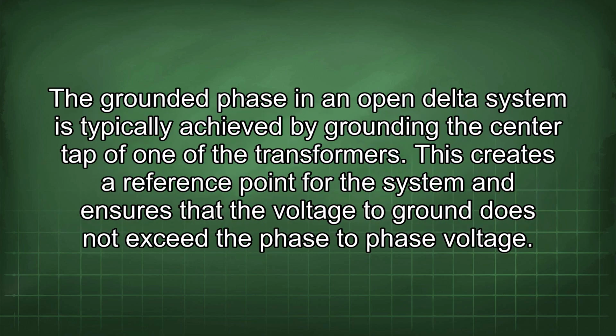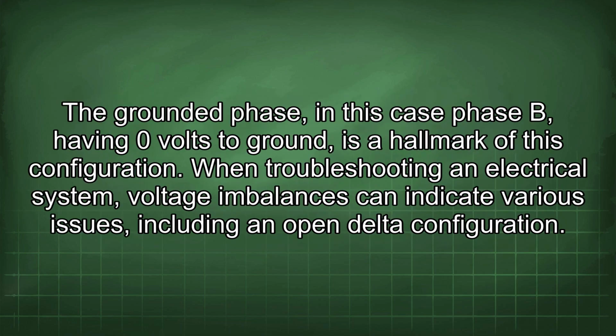The grounded phase in an open delta system is typically achieved by grounding the center tap of one of the transformers. This creates a reference point for the system and ensures that the voltage to ground does not exceed the phase-to-phase voltage. The grounded phase, in this case phase B having 0 volts to ground, is a hallmark of this configuration. When troubleshooting an electrical system, voltage imbalances can indicate various issues, including an open delta configuration.